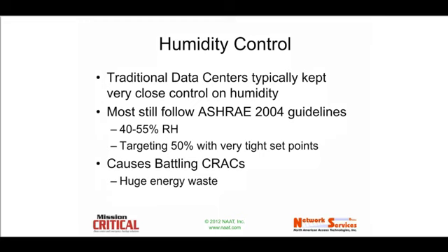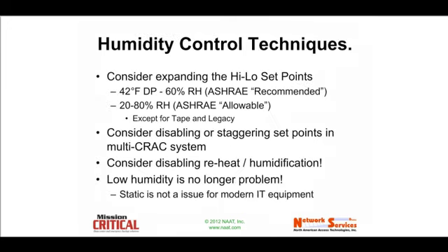Humidity control, of course, is a concern to all of us, and it does require mechanical cooling and dehumidification. It's very common to have battling CRACs. It's a subject in itself. So even if we're using outside cooling or inside cooling, we do want to try to broaden the envelope and not have battling CRACs. Essentially, we want to try to minimize the number of units that are rehumidifying and dehumidifying simultaneously in a room. But if we're doing outside air control, we're going to have a centralized control system.